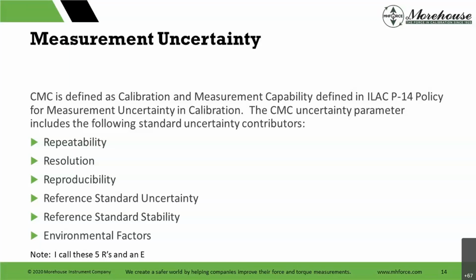So why is that important? For those that are following, and some are new, setting that resolution or taking it into account is important because as calibration providers or as users, we could set a coarse resolution and make everything perfect. So if I have a 100-pound load cell that I'm using to weigh things, and at 0.01 I can detect changes on my scale, and I set my scale to 100.1 and I put things on and off, my uncertainty could get a lot better if I don't have any deviation when I calculate it. Therefore, resolution should kick in and say, hey, if I want to count by 0.1, I should add that to my uncertainty budget, right? If I want to count by 0.01 and I'm showing like half 0.05 deviation, maybe you can convince somebody that, okay, it's accounted for in that.